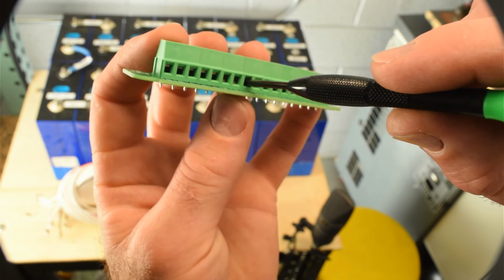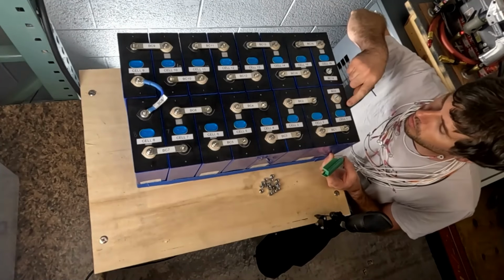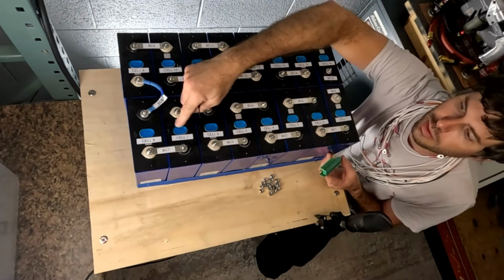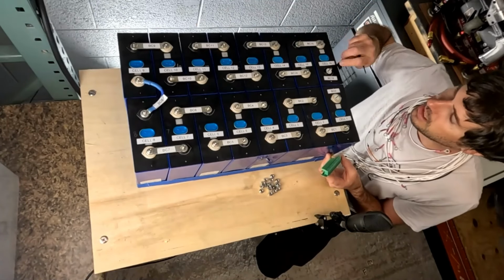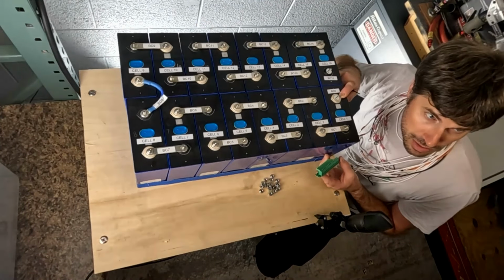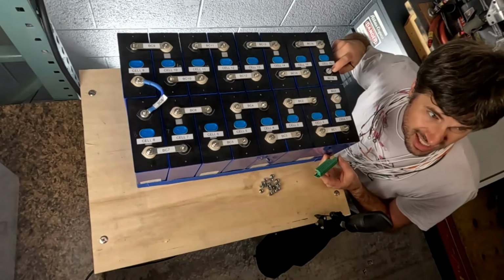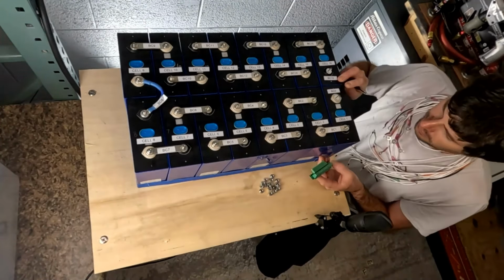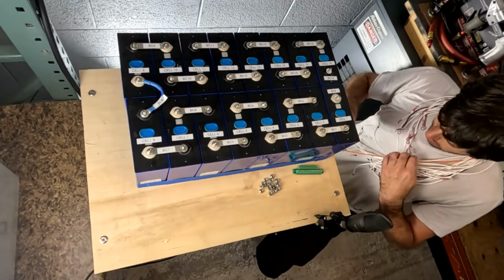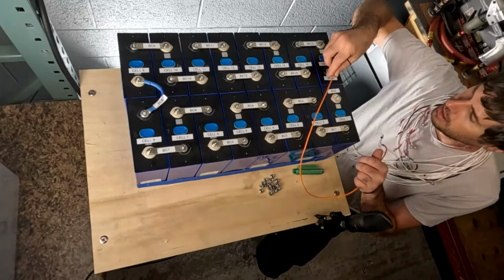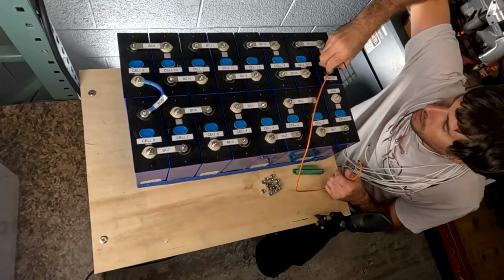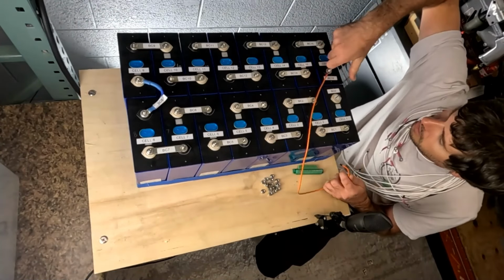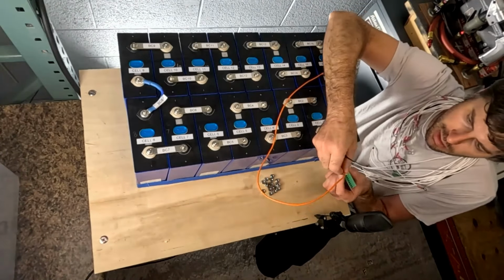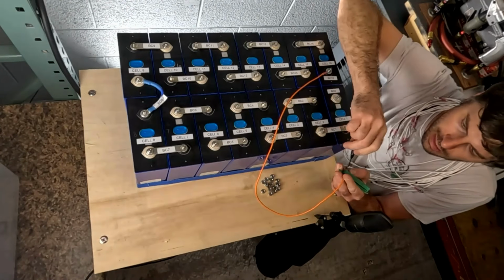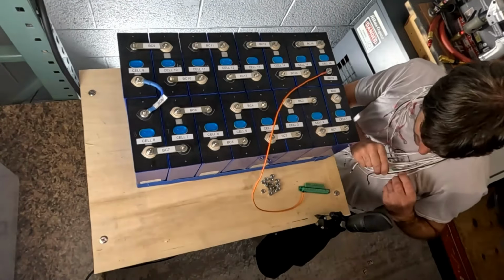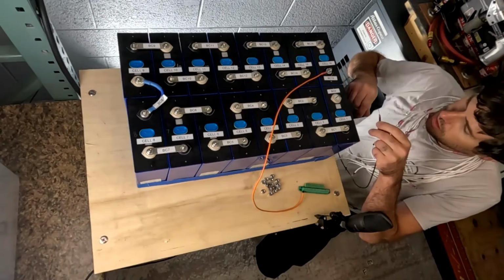The way I have my cells laid out here is I've started with cell number 1, and it goes all the way down this way to cell number 8 and all the way back to cell 16. So my most negative connection, that's BC0, and my most positive connection, that's BC16, are both on this end of the battery. I'm going to go ahead and start with my orange wire and use that for BC16. For the moment, I'm going to put these nuts on finger tight, and then with each wire I'm going to stick it in the terminal block and tighten it down. Next I'm going to use my black wire and put that on BC0.